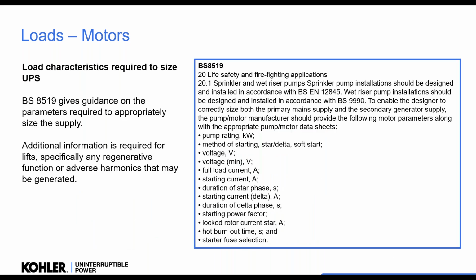So where we do have the motor loads, we need a certain amount of information to be able to size that inverter, that UPS. All the information we need to size that correctly is recommended in 8519. It's difficult to get, but very, very important that we do have it, so we can make sure we size it absolutely correctly.